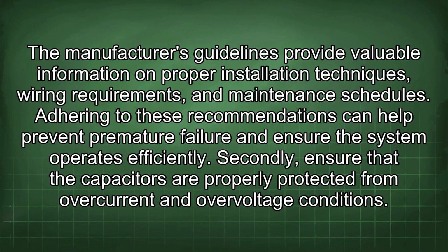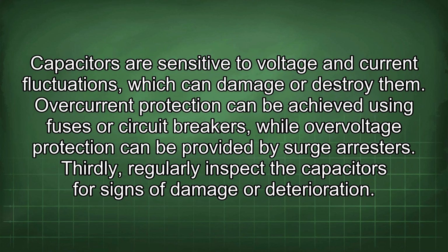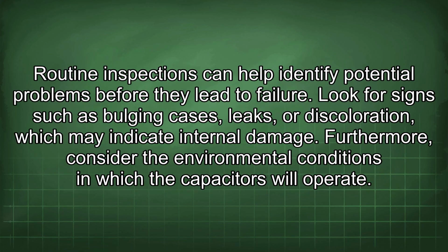Secondly, ensure that the capacitors are properly protected from overcurrent and overvoltage conditions. Capacitors are sensitive to voltage and current fluctuations, which can damage or destroy them. Overcurrent protection can be achieved using fuses or circuit breakers, while overvoltage protection can be provided by surge arresters. Thirdly, regularly inspect the capacitors for signs of damage or deterioration. Routine inspections can help identify potential problems before they lead to failure. Look for signs such as bulging cases, leaks, or discoloration, which may indicate internal damage.